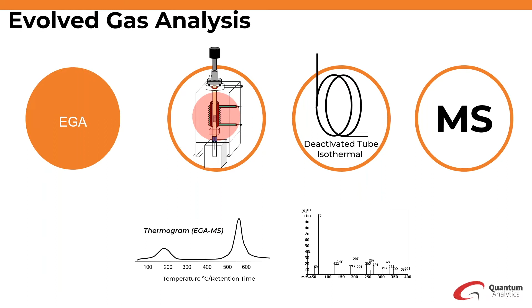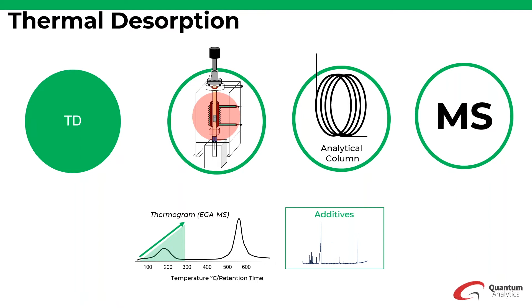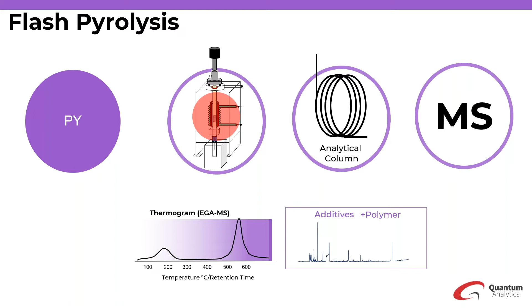This EGA thermal profile will really facilitate how we navigate the other modes of operation. For example, in thermal desorption, we switch to an analytical column this time. The sample cup is dropped, the temperature is ramped, just like in EGA, but we now have separation of all of the pyrolysates that you thermally sampled, and you get a nice chromatogram at the end. This is really ideal for things like additives or any lower molecular weight compounds that you may want to thermally desorb out of your sample. In flash pyrolysis, the sample cup is dropped into a heated furnace and it's sampled isothermally. The result is a pyrogram of the various components in your polymer that was pyrolyzed at whatever temperature that you programmed it to. In this particular example, you have your additives and your polymer that's coming out at that particular pyrolysis temperature.